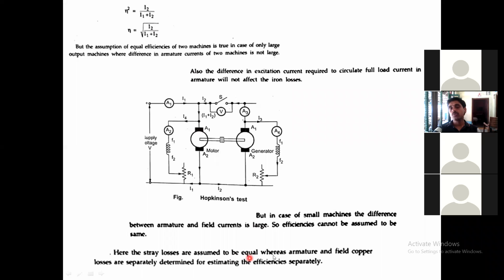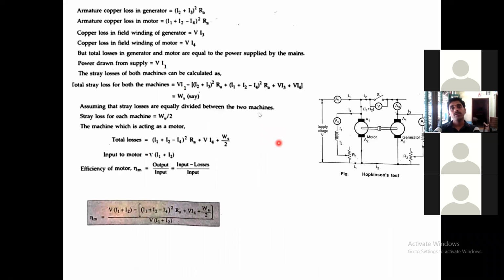The stray losses are assumed to be equal, whereas armature and field copper losses are separately determined. Here stray losses are the same for both the identical machines, but armature losses you have to calculate separately. So coming to the armature losses, armature copper loss of the generator, the current in the armature, what is that? I2 plus I3 whole square into RA. What is the armature copper loss in the motor? What is the current in the armature? This is I4, this is I1 plus I2. I1 plus I2 minus I4 is the current in the motor.